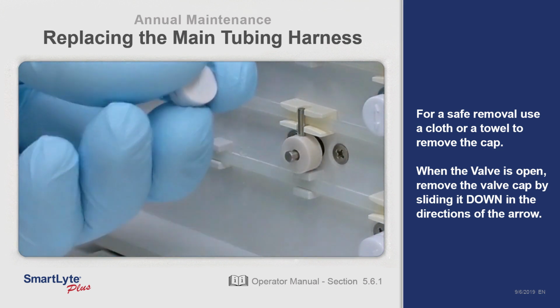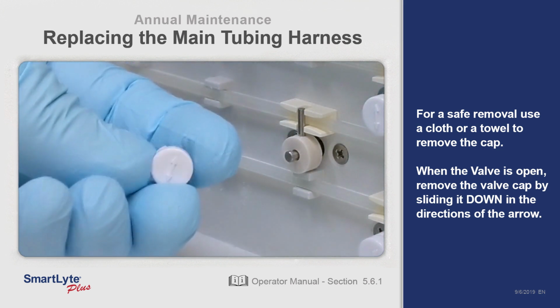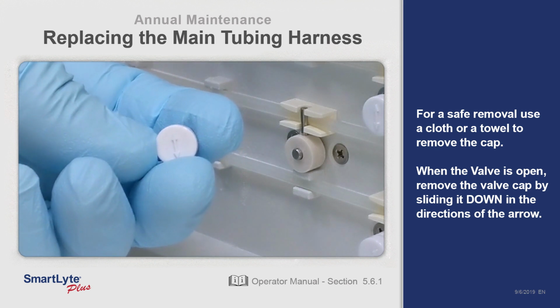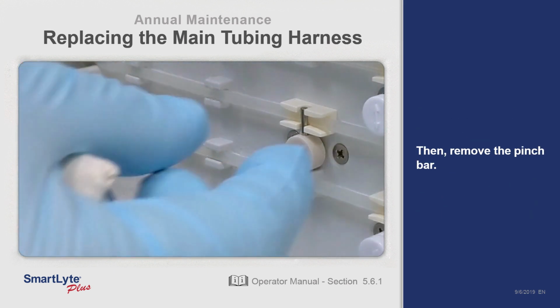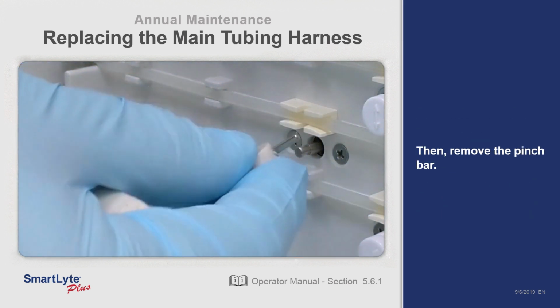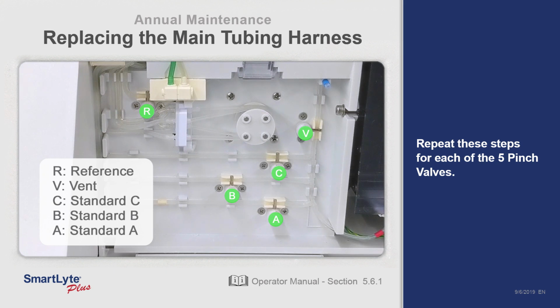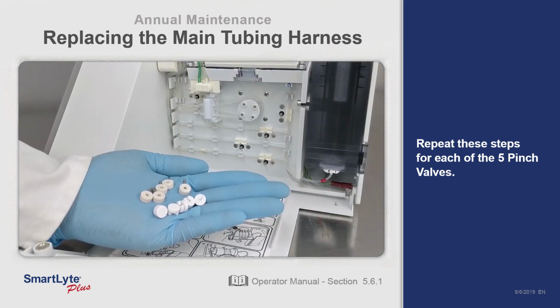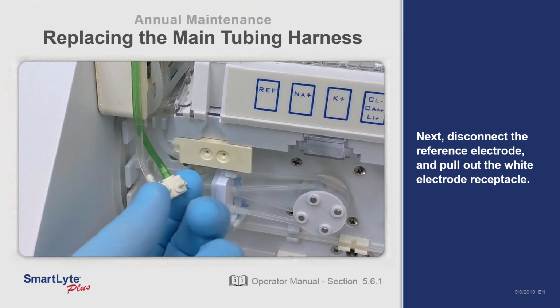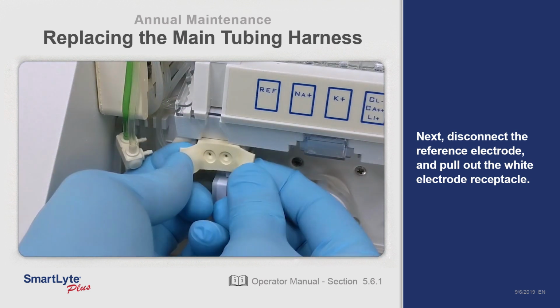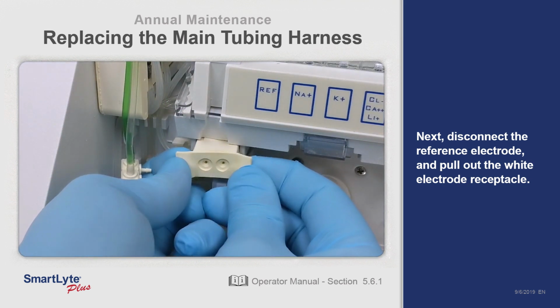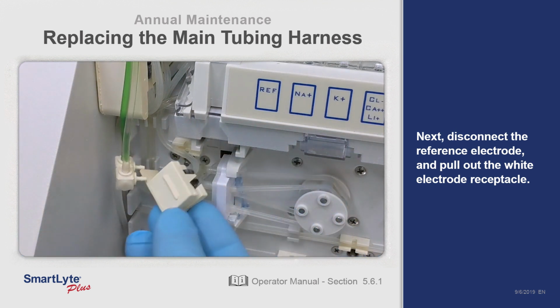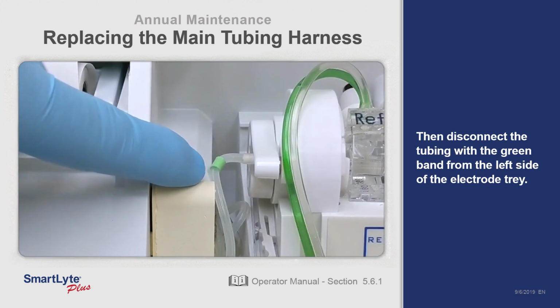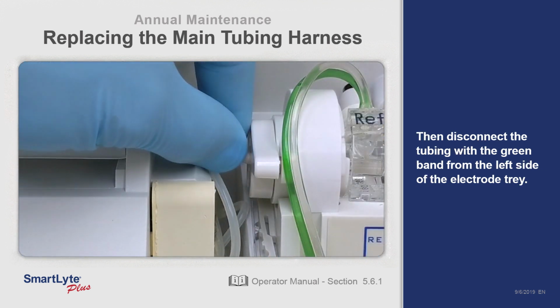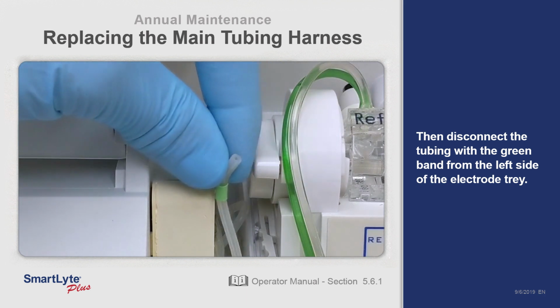When the valve is open, remove the valve cap by sliding it down in the directions of the arrow. Then, remove the pinch bar. Repeat these steps for each of the 5 pinch valves. Next, disconnect the reference electrode and pull out the white electrode receptacle. Then, disconnect the tubing with the green band from the left side of the electrode tray.